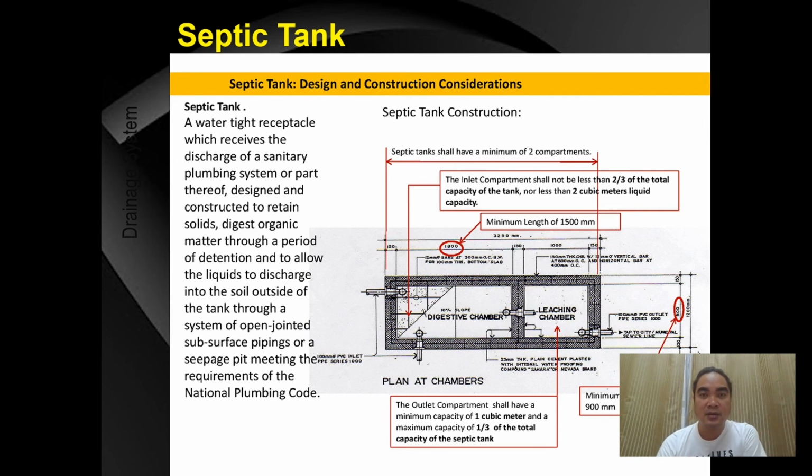The tank design and construction consideration. Septic tank, the watertight receptacle which receives the discharge of the sanitary plumbing system or part thereof, designed and constructed to retain solids, digest organic matter through a period of detention and to allow the liquid to discharge into the soil outside of the tank through a system of open-jointed subsurface piping or a seepage pit meeting the requirements of the plumbing code.